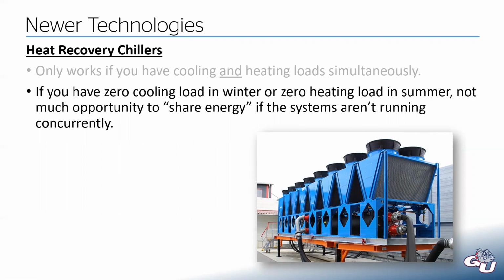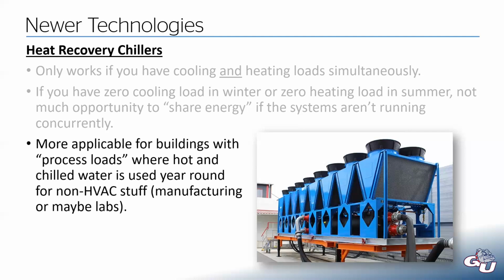There isn't a lot of opportunity there to share energy because whenever the chillers are running, the boilers are off, and vice versa. So this is going to be more applicable for buildings that have what are called process loads, which is essentially saying any loads that are non-HVAC related. So you could have a factory that needs to use hot water in whatever machinery you're running to make whatever product you're making in there.